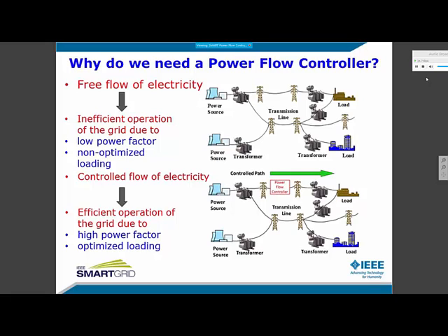We all know that electric current flows through the path of least impedance. This free flow of electricity from the sources to the loads makes the grid operate inefficiently because of low power factor, non-optimizing loading, and so on. The power flow controller controls the flow of power in a transmission line, resulting in an efficient operation of the grid. While maintaining the voltage stability, if the reactive power flow is reduced, the loss in the power grid can be reduced, resulting in less global warming.